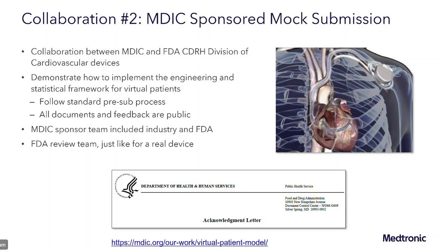So the way that this worked was we had a sponsor team. So this was a hypothetical firm. And it was actually composed of people from different companies around the medical device industry, as well as representatives from FDA that we worked together. We described this clinical study and our hypothetical new device that we were going to investigate. And then there was a review team. So FDA actually set aside time for employees to participate in the review of this mock submission. The documents here are available on the MDIC website. It's definitely an interesting read, worth looking at.